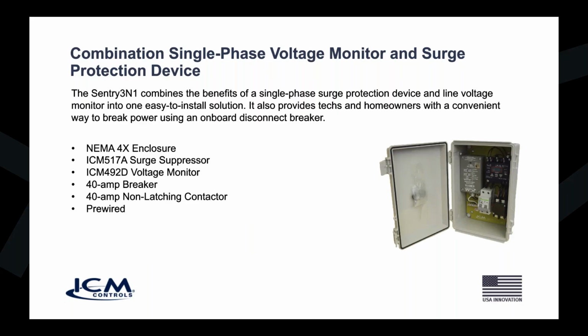So this comes included with a NEMA 4X outdoor rated enclosure. It has built into it the 517A surge suppressor. That one's got 100,000 amps maximum surge capacity, so a little more than the 517A Lite. And it's built into a rugged metal box that can handle severe surges a little bit better than plastic. So that's some features there.